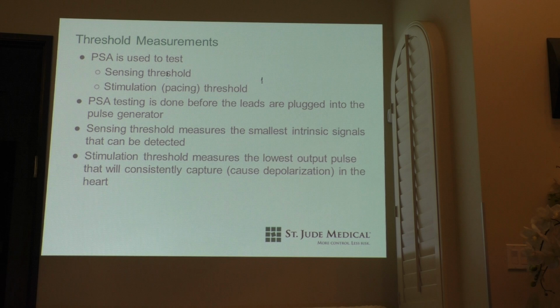And so we do high output pacing. We pace at 10 volts, which we would never pace through a pacemaker. And we just make sure that we're not capturing anything that way. So we say, okay, 10 volts. The physician will feel for diaphragmatic stimulation on both sides, which is just vigorous hiccuping. You're slamming the diaphragm instead of a smooth motion. They move quickly.